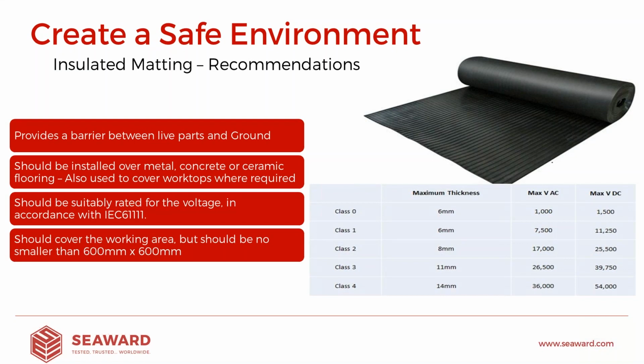Well, the next question is always, what kind of rubber matting should we be looking to use? Well, there is an international standard for rubber matting, which is IEC 61111. And you'll see on the table here, this table is taken from IEC 61111. And you'll notice that there are different classes of rubber matting. And those different classes relate directly to the voltage withstand potential of the rubber matting. You'll notice there is a 7,500 volt and 11,250 volt DC for class 1 rubber matting.